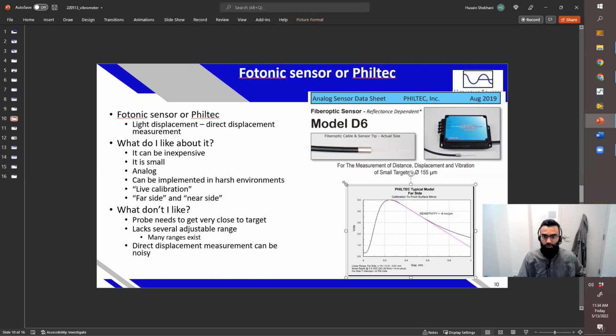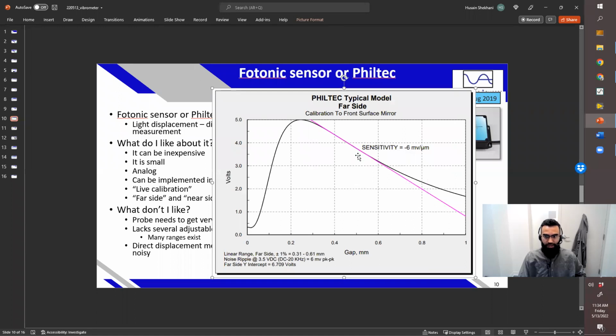But here, with this type of sensor, this is called, I think, a D-type sensor. The RC sensor is the reflection independent one. They use two probes right next to each other in order to cancel out the reflection dependence. But in this one, there's not that cancellation. It's a little bit cheaper for that reason. And you have to find that maximum point and dial it in. That's how you calibrate. You don't necessarily have to look for the exact 0.25 gap, thinking that's where I need to get 5 volts. No, you just need to look for where the maximum is, dial that into 5, and you already know you're at 0.25 when you're at the maximum.